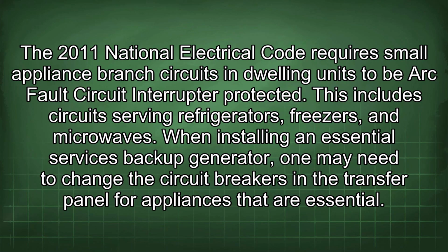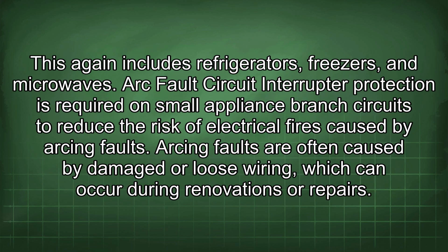The 2011 National Electrical Code requires small appliance branch circuits in dwelling units to be arc fault circuit interrupter protected. This includes circuits serving refrigerators, freezers, and microwaves. When installing an essential services backup generator, one may need to change the circuit breakers in the transfer panel for appliances that are essential. This again includes refrigerators, freezers, and microwaves.